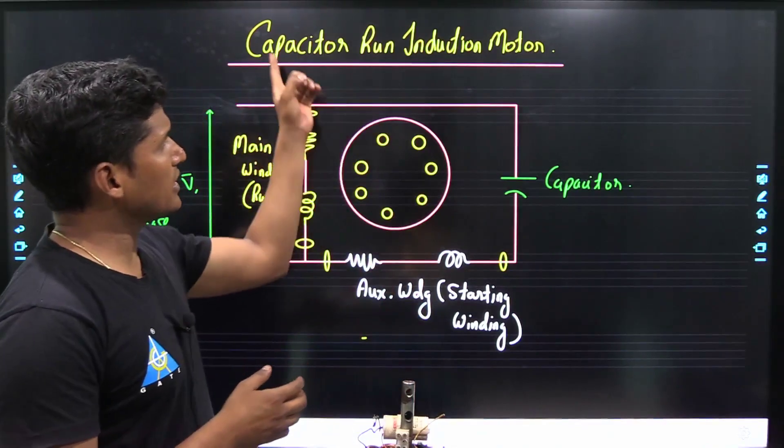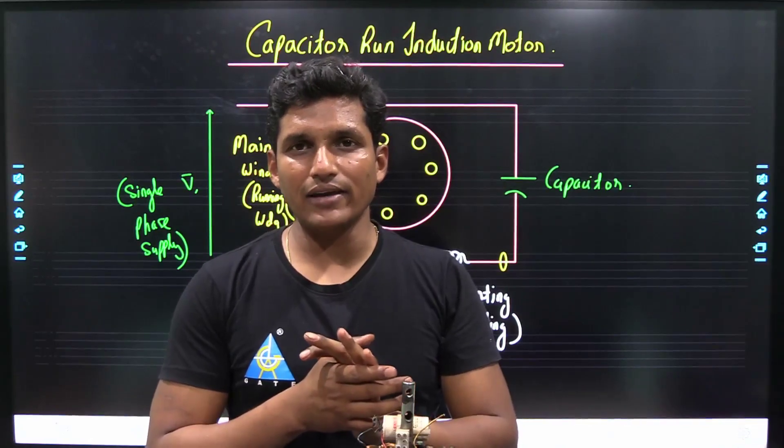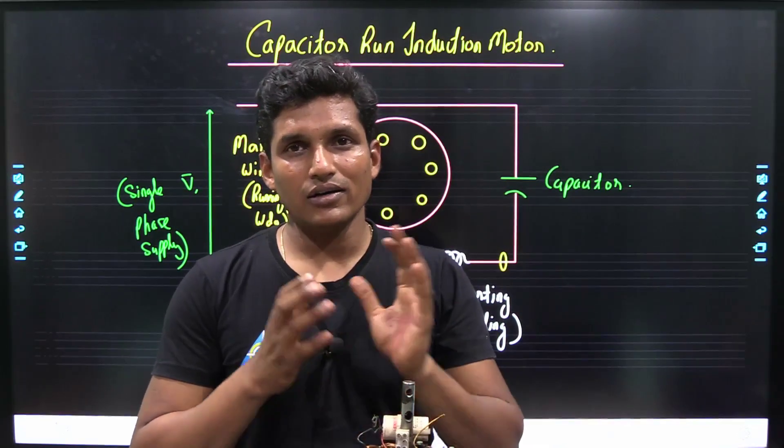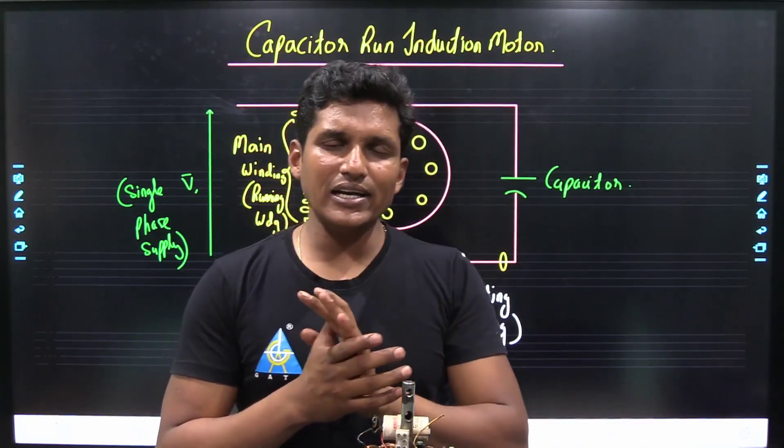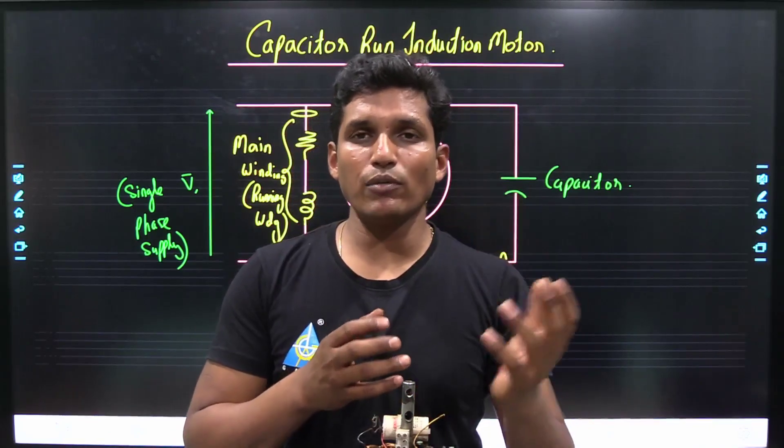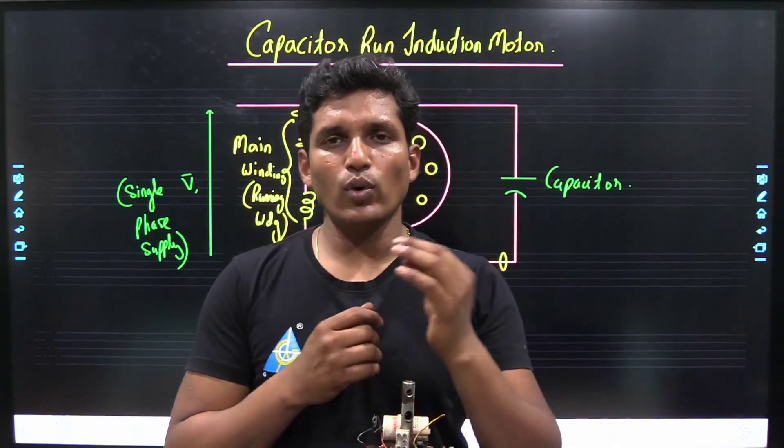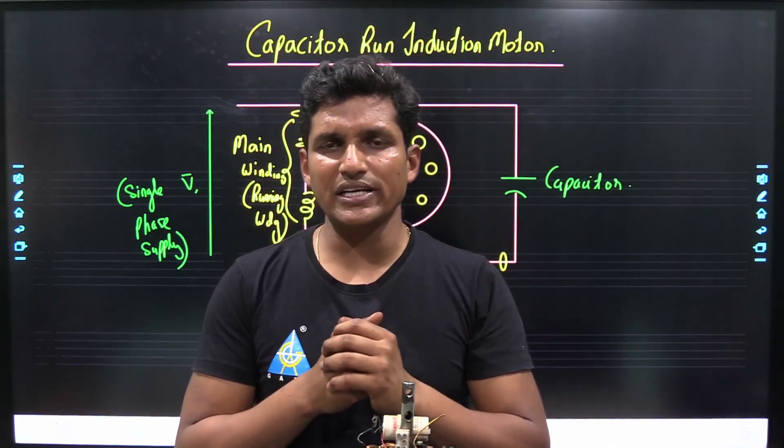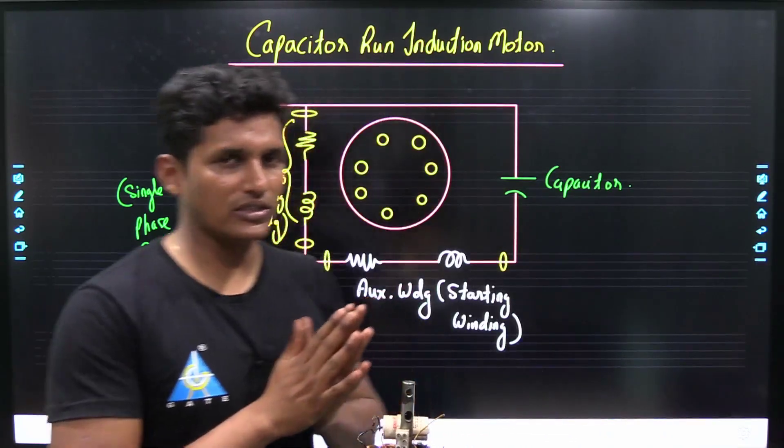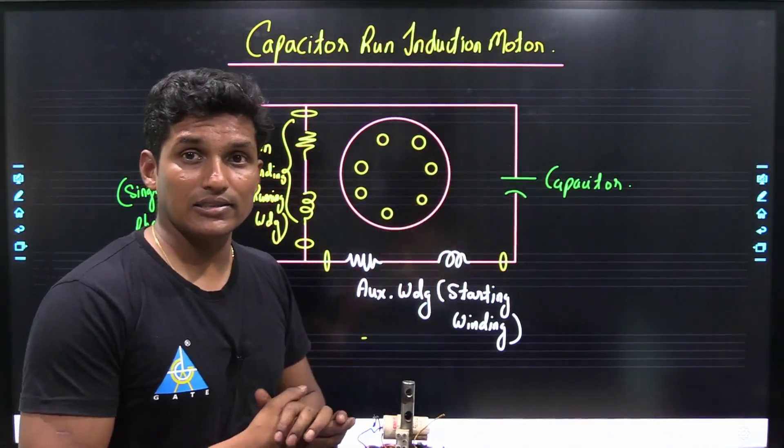In capacitor run induction motor, by the name it is specified that capacitor is permanently connected to the circuit. In capacitor start induction motor, capacitor is connected at the time of starting, but with the help of centrifugal switch, when the speed reaches 70 to 75 percent of the synchronous speed, it is disconnected from the circuit. But in capacitor run induction motor, capacitor is permanently connected in the circuit.